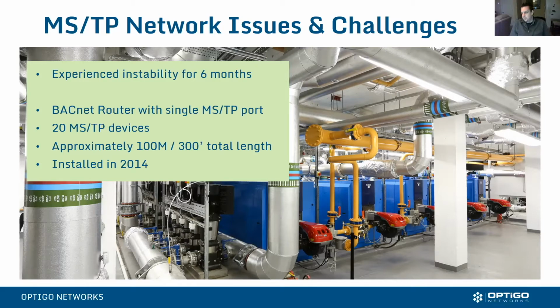Interesting. So what was the impact on your overall system performance, your day-to-day runtime? While the impact wasn't hugely notable for the devices running, like the pumps, because we tend to use traditional hardwired signals for those, the impact was more in relying on the data for use in other applications. That's where the reliability was falling down for us. We couldn't rely on the data we were receiving.